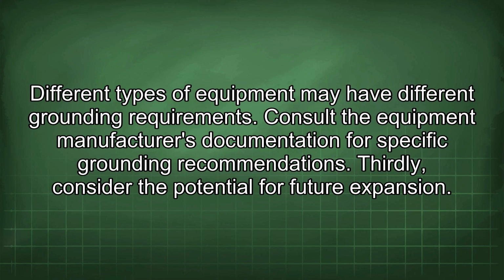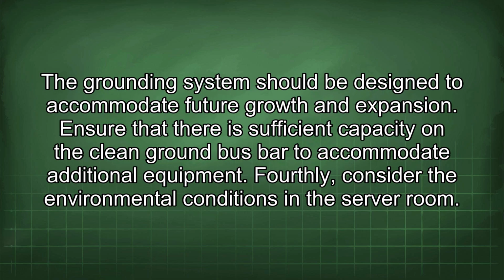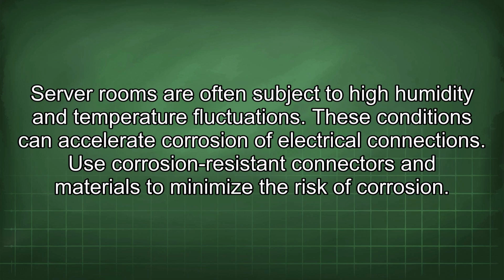Thirdly, consider the potential for future expansion. The grounding system should be designed to accommodate future growth and expansion. Ensure that there is sufficient capacity on the clean ground bus bar to accommodate additional equipment. Fourthly, consider the environmental conditions in the server room. Server rooms are often subject to high humidity and temperature fluctuations. These conditions can accelerate corrosion of electrical connections. Use corrosion-resistant connectors and materials to minimize the risk of corrosion.